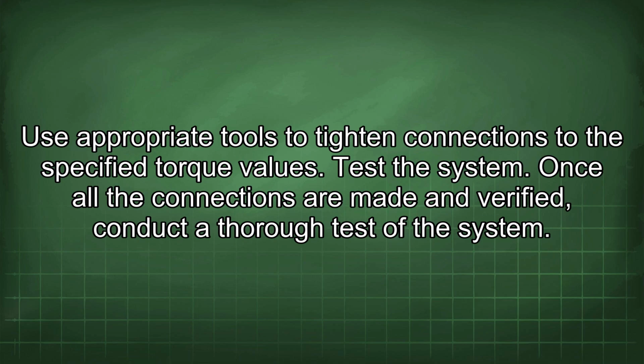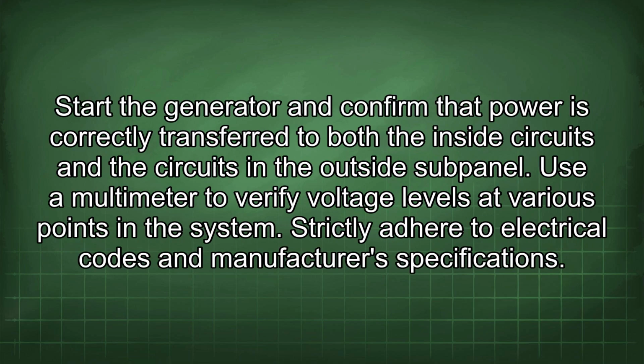Test the system. Once all the connections are made and verified, conduct a thorough test of the system. Start the generator and confirm that power is correctly transferred to both the inside circuits and the circuits in the outside subpanel. Use a multimeter to verify voltage levels at various points in the system.